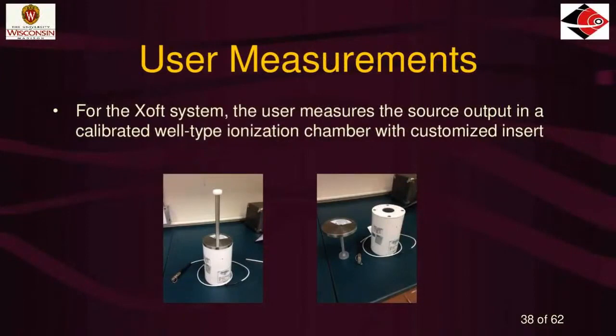For Xoft, the output is based on air kerma rate at 50 centimeters, but since nobody in a clinic is going to actually measure that, the user will use a well chamber. Every day before treatment, a Xoft user puts their source inside a well chamber using a special metal insert that holds the source in place vertically and positions it inside the chamber. This allows you to verify the output of your source daily and apply a calibration from the ADCLs for this well chamber.